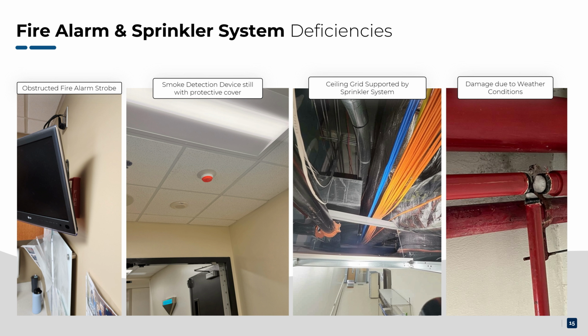The next picture shows an orange protective cap over a smoke detector, likely left over from a construction project, that could hinder the device's function. But some issues aren't always visible. Above the ceiling, construction crews sometimes use these systems as support, for example, using sprinkler piping to hold up the ceiling grid. That's a big problem. Another less obvious factor is weather. In our last example, insufficient heating in the stairwell allowed the sprinkler piping to freeze, causing bursts and water leaks.